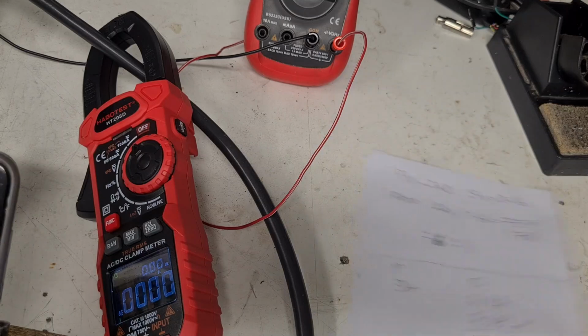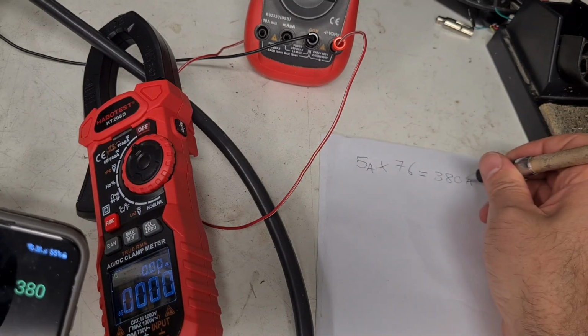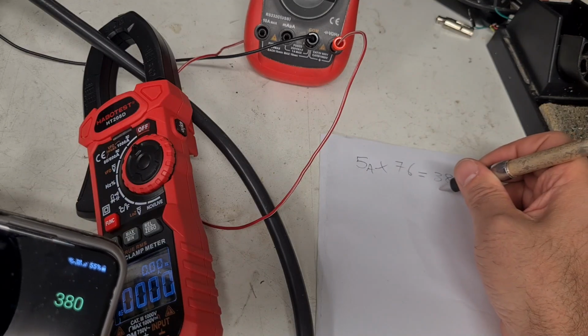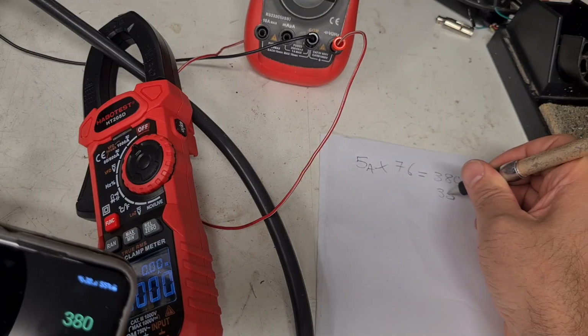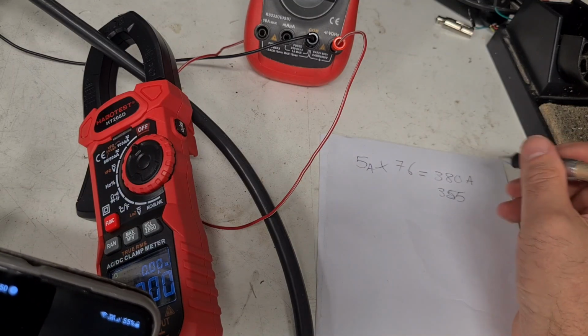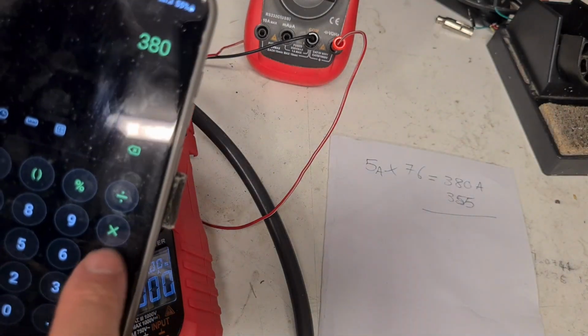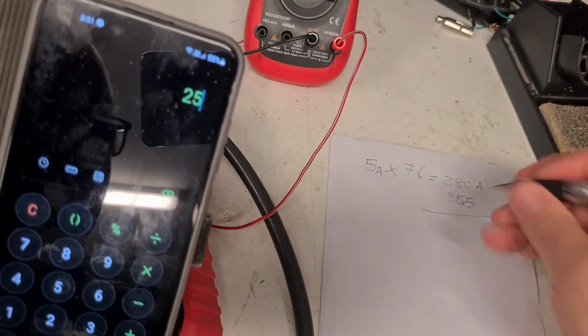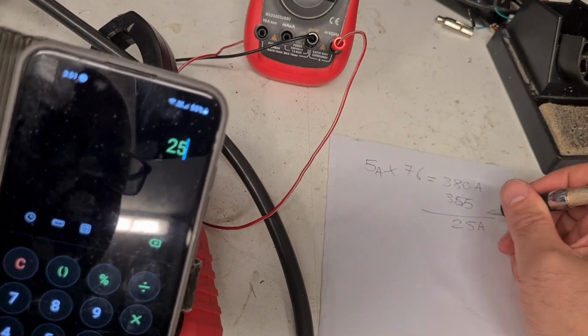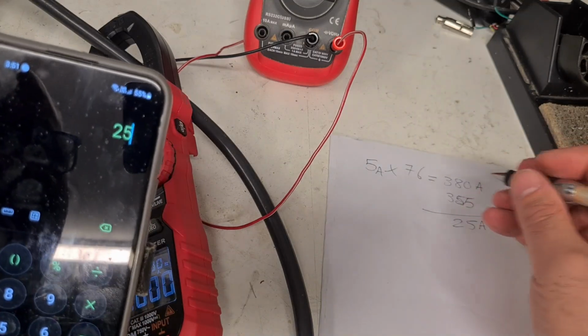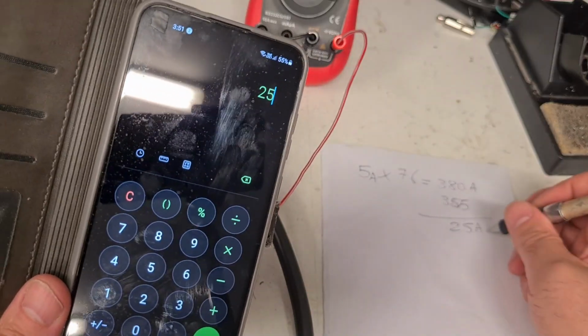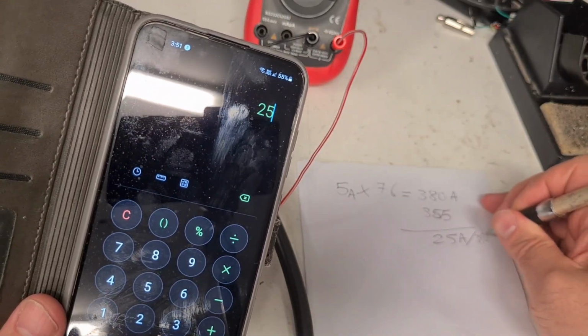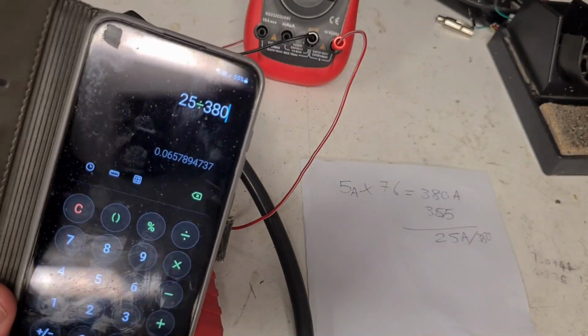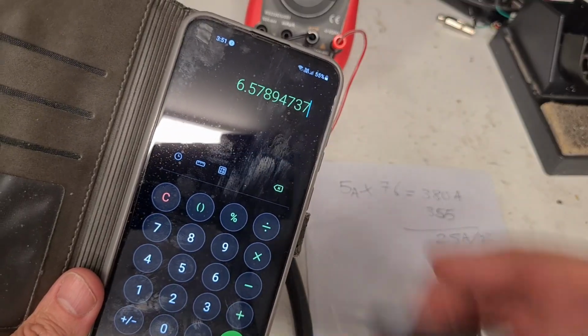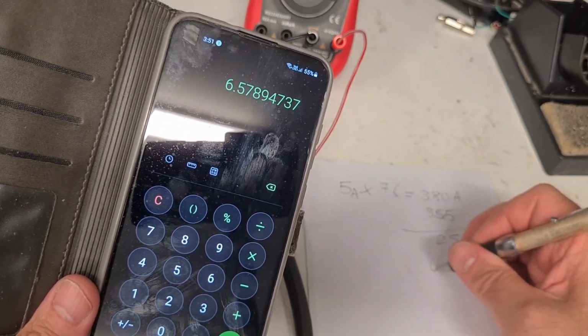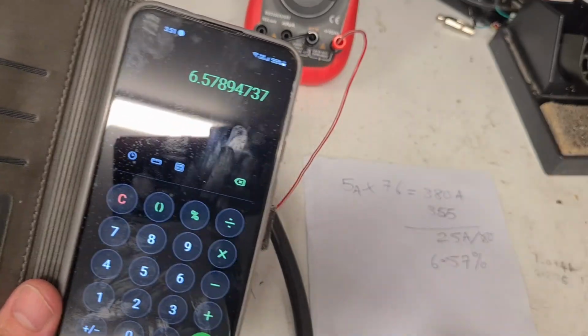352 amps. Okay. Now, if we minus 380, 352, technically, right, I want to work it out at 355 because the wire started heating up because it was on for a long time. I want to see what that is. Minus 355 is 25 amps I lost. So then we do 25 divided by 380 times 100, 6.5. So the ratio now is 6.57% less. What was it before?